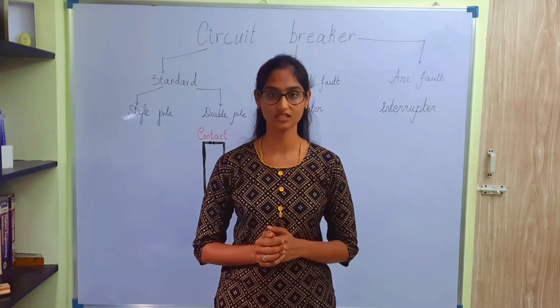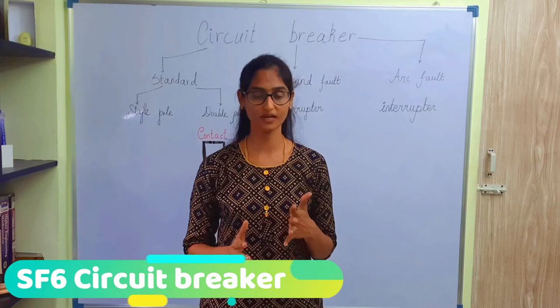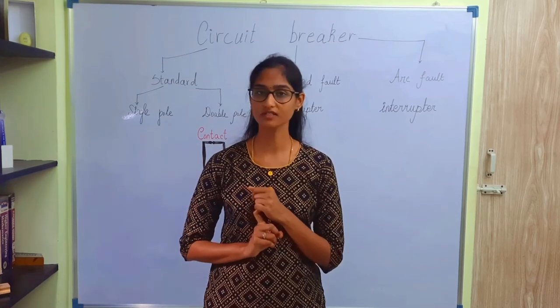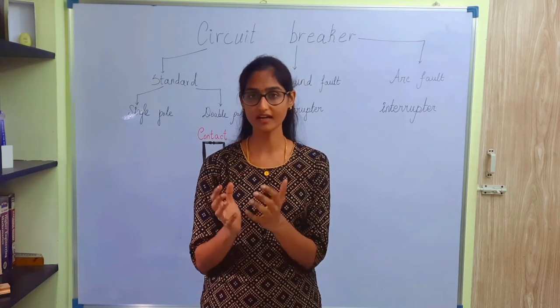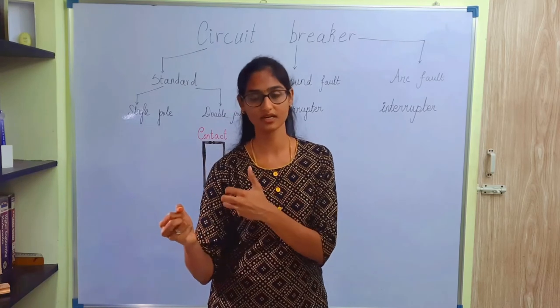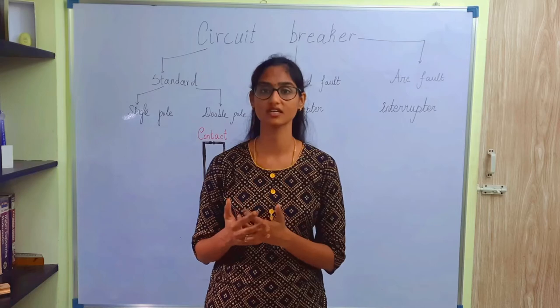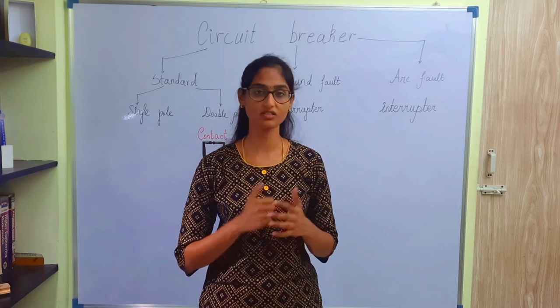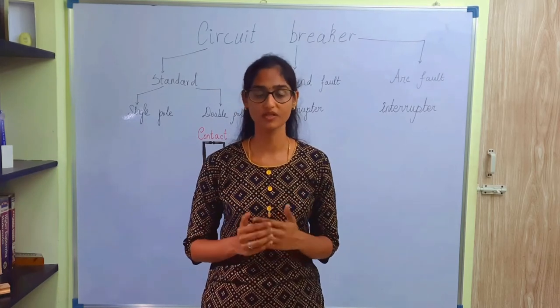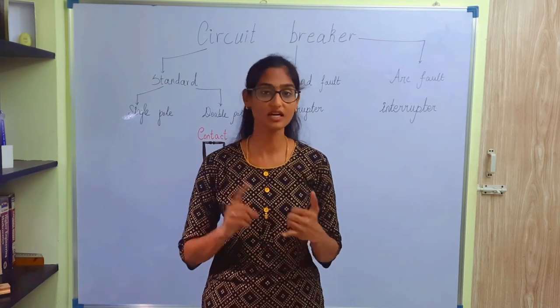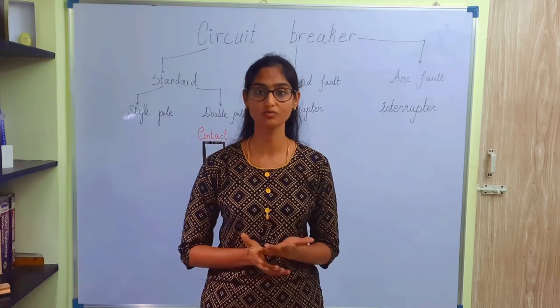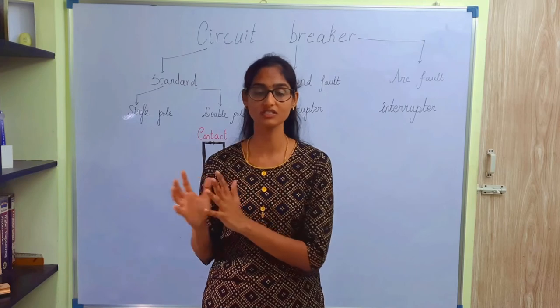Let us discuss about SF6 circuit breaker. The sulfur hexafluoride or SF6 is capable to extinguish current because of its electronegativity. What is electronegativity? Electronegativity is when an atom is capable of pulling the electrons from the neighboring atom to that atom. That capability is called as electronegativity or the tendency to be more electronegative so that it will attract the electrons from the neighboring atoms to it. SF6 or sulfur hexafluoride is a highly electronegative element. So for that reason, we are using it in circuit breakers. There are other advantages too. It is not inflammable and it is safe to use and it is odorless. So it is very stable at room temperature too. That is why we are using it very safely in circuit breakers.